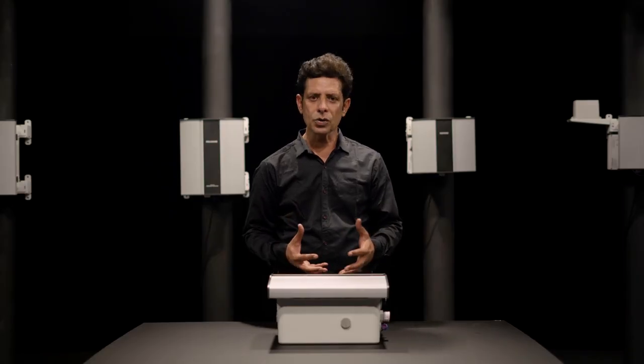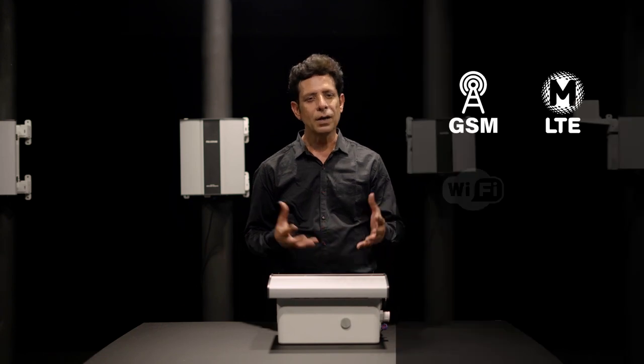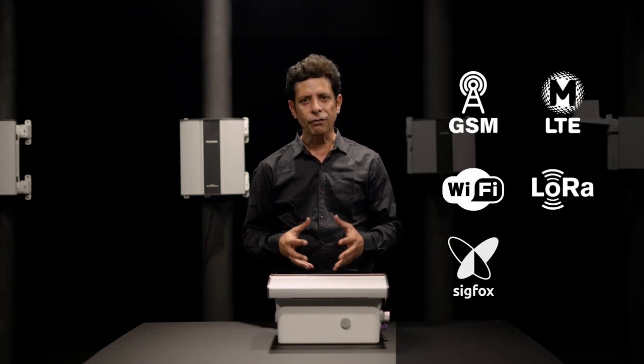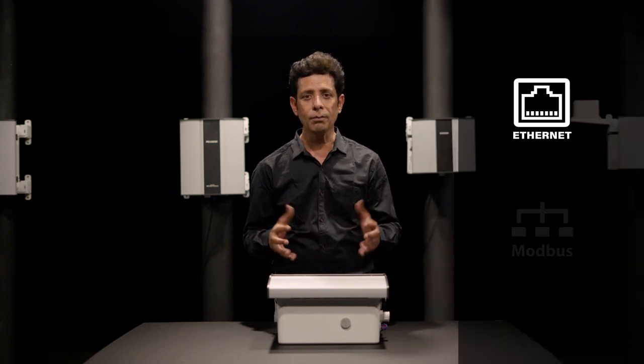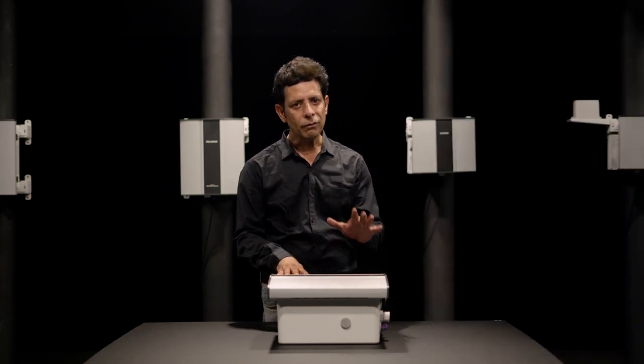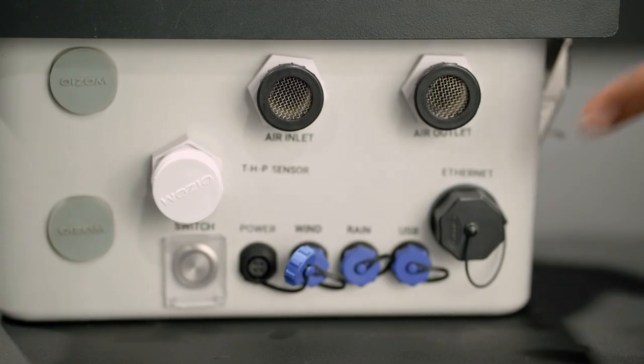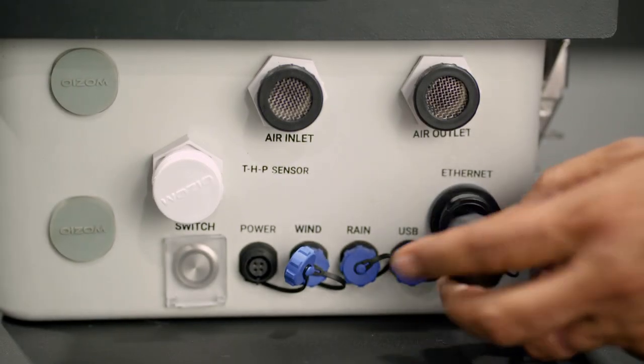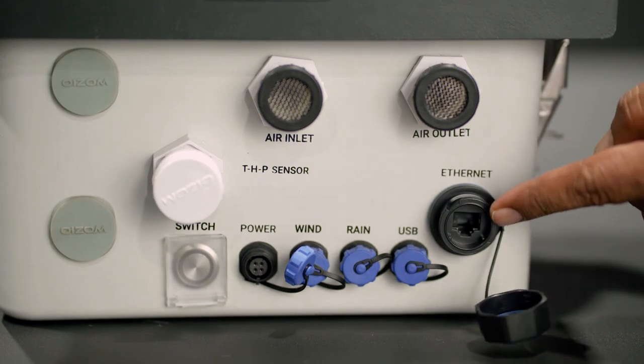For data communication, Odosense is available with range of wireless options like GSM, Wi-Fi, LoRa, Sigfox, narrowband IoT and wired options like Ethernet and Modbus. This equipment, which I have with me, is our GSM variant, whereas this is the RJ45 port for Ethernet-based connectivity as a secondary communication.